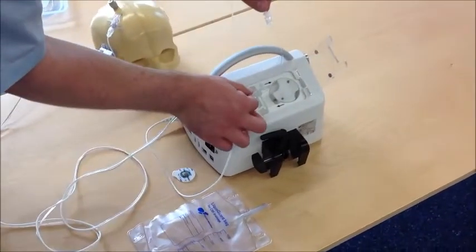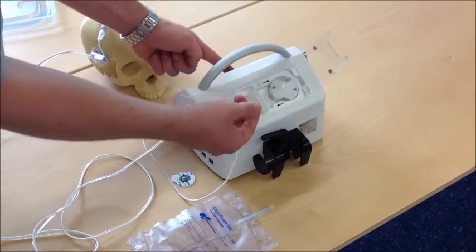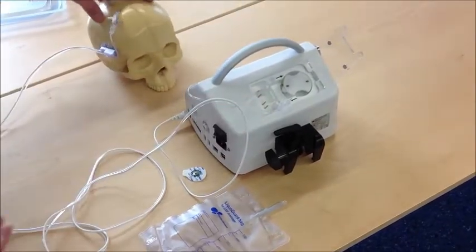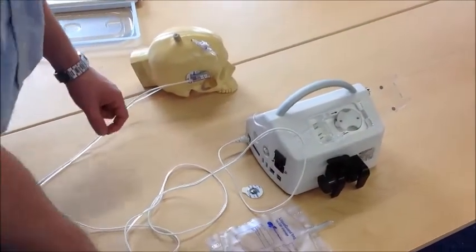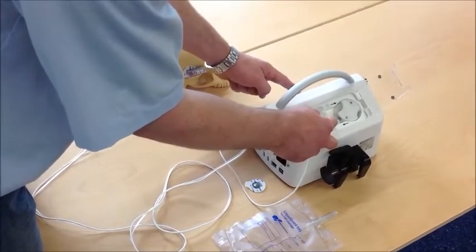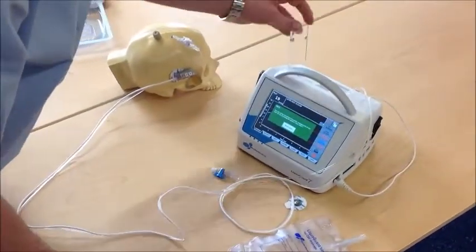Those two arrows are given here again. Insert the first connector into the pump. Press the button. Hold the tube set loose. It is automatically loaded. Meanwhile, CSF is aspirated from the patient, flushing the tube set. Attach the second connector. Close the cover clasp.